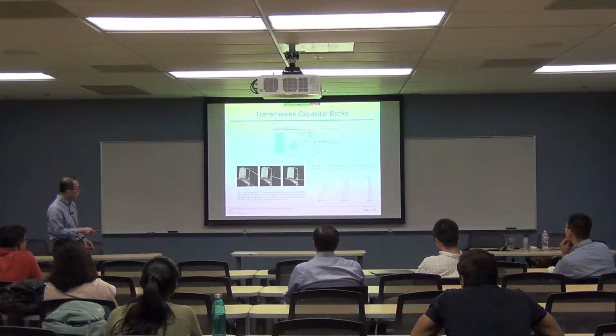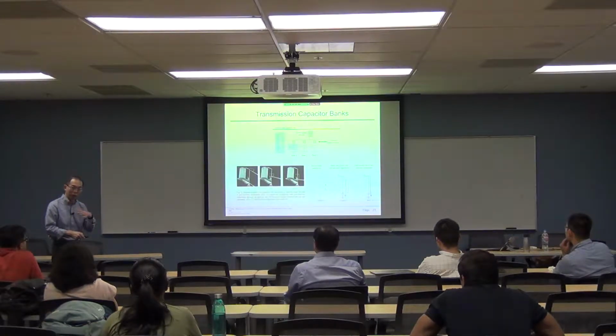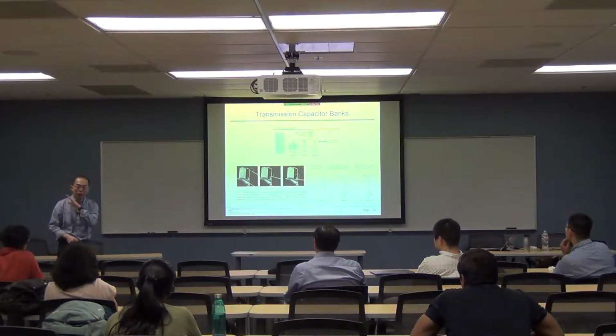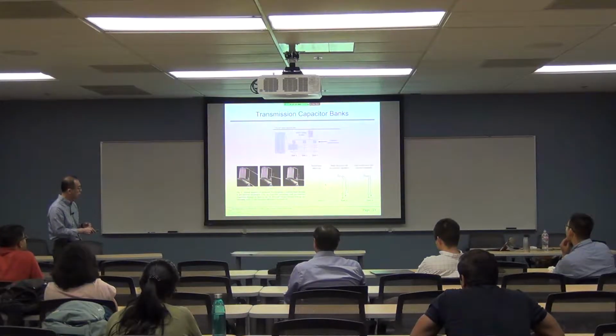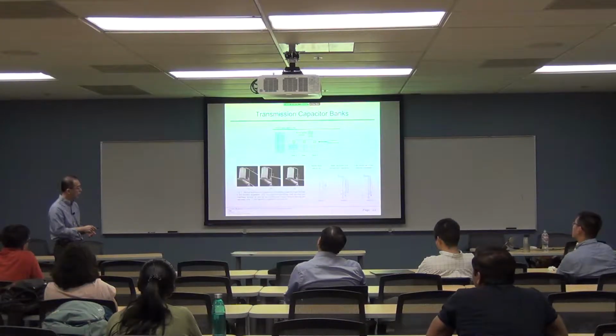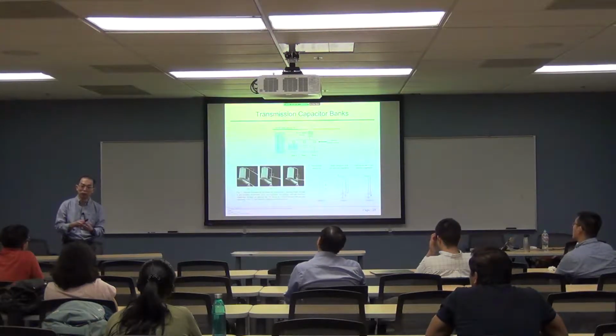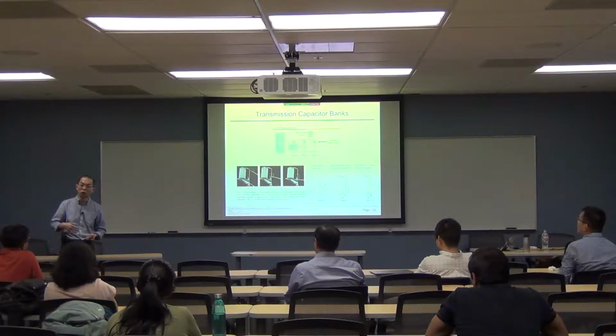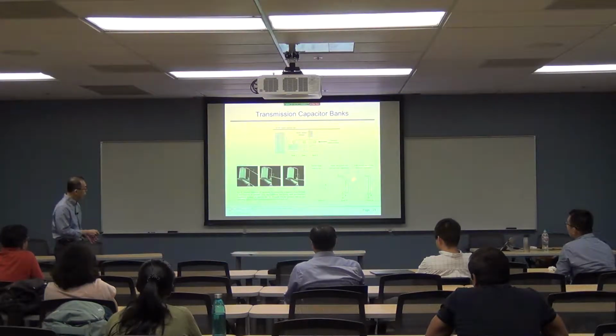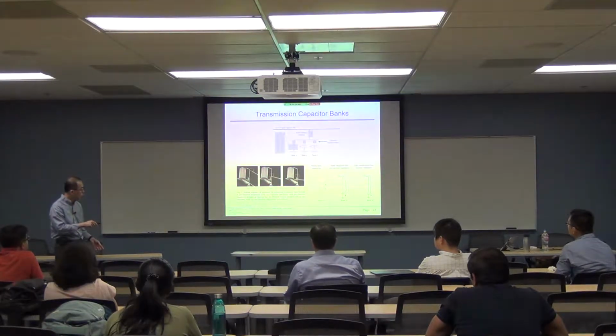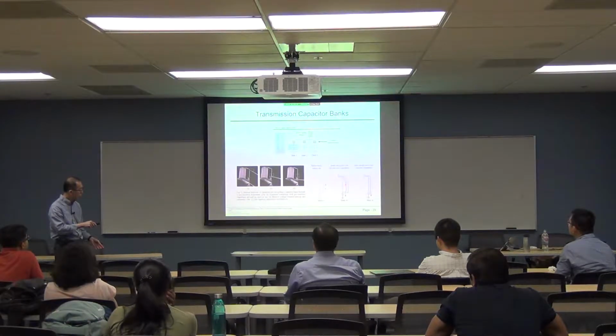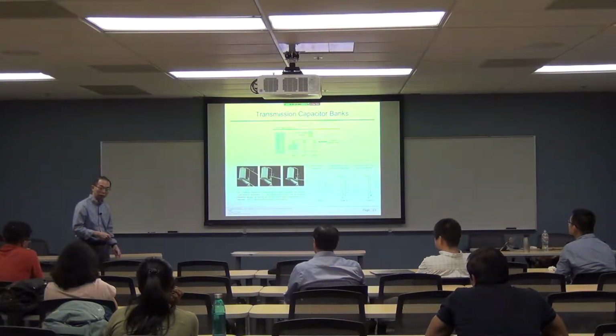In here you can see this is the capacitor, one of the capacitors, and let's assume that in that bank there is no other capacitor online at this moment. Our job is to energize this, but the way we energize it is that we want to minimize the transients and also the inrush current. So the way it works is that we switch into here, so that the current flows through here and then down to here. Therefore you minimize the transients.